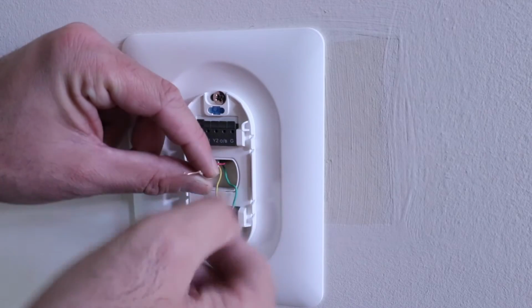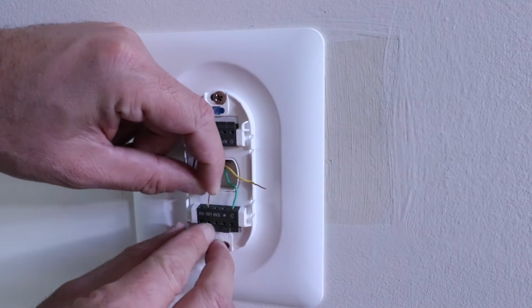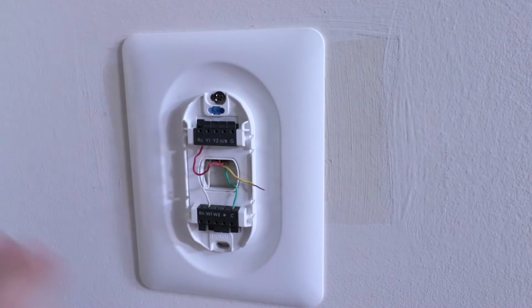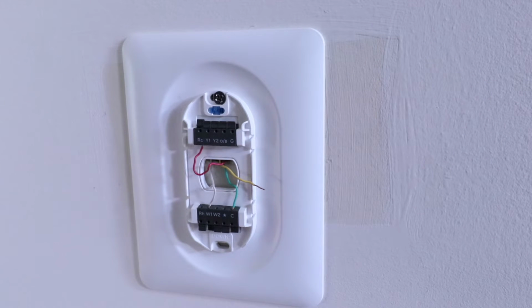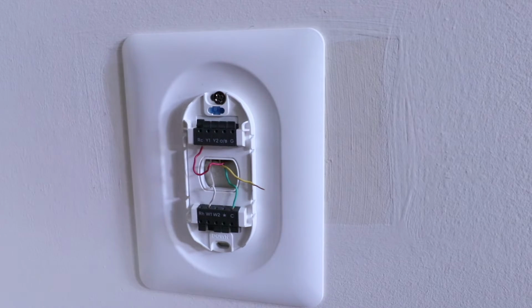Now we've got our W wire. We're going to go ahead and connect that to W1. And the reason we connect it to W1 instead of W2 is because W1 and W2, the 2 is if you have dual stage heating or dual stage cooling. So the W is the heat terminals. We only have single stage heating. If we had dual stage heating, W1 and W2, we would then connect both of those. But in most cases, you're just going to have one W1 terminal. So we're going to put that wire there because that's what we had, just one W wire.